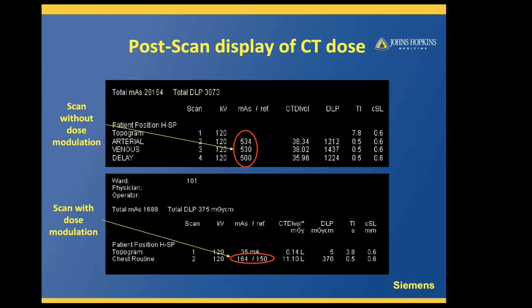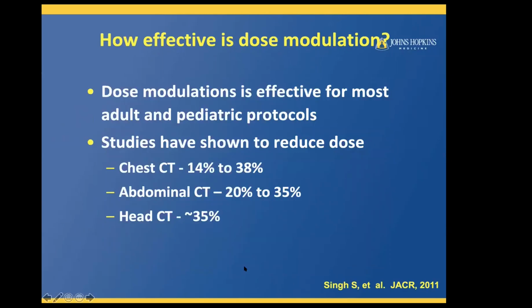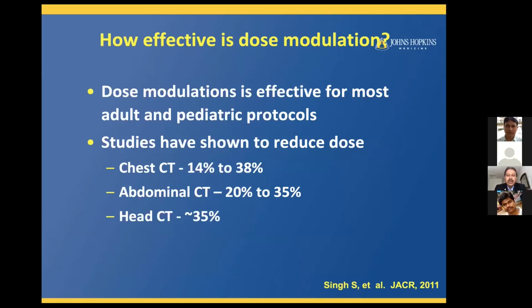If you're doing a scan with dose modulation, the final report looks more like this one. It tells you it is 164 mAs based on a reference mAs of 150. What it means is each scanner has built-in curves for utilizing the tube current based on the patient thickness within a certain desired range, and that's what this is showing. Dose modulation has been very effective. In fact, it is now almost a requirement that all the CT scans we do have dose modulation turned on, because without doing anything, the scanner will automatically determine the dose required and reduce the dose by quite a considerable amount.